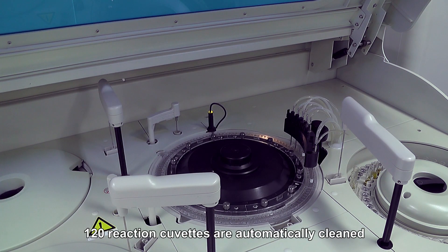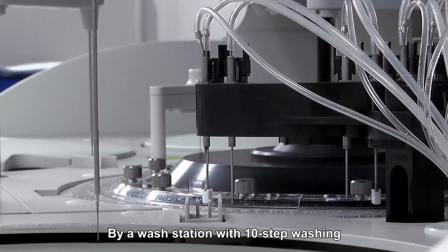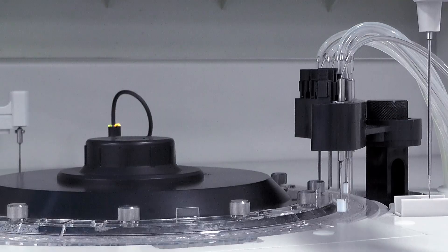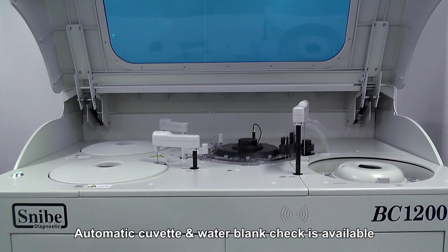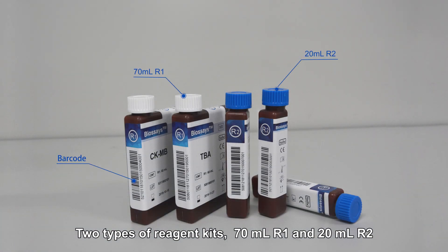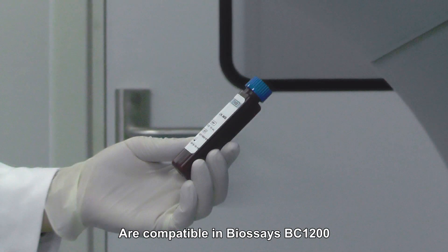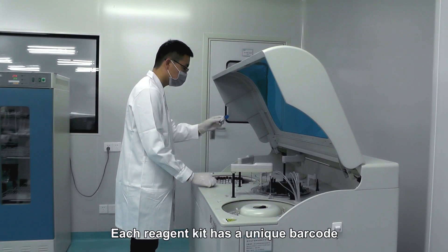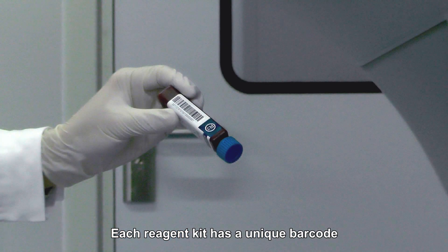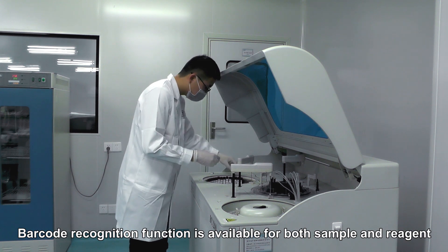120 reaction cuvettes are automatically cleaned by a wash station with 10-step washing. Automatic cuvette and water blank check is available. Two types of reagent kits — 70 milliliters R1 and 20 milliliters R2 — are compatible in Biossays BC1200. Each reagent kit has a unique barcode; barcode recognition function is available for both sample and reagent.